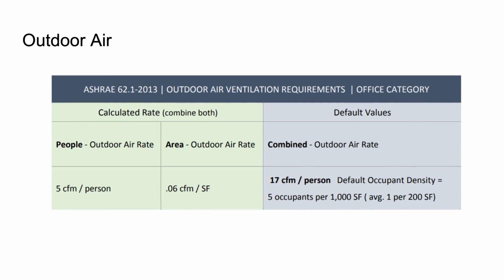Yeah, so if you have a vestibule, like an intermediary space, that's not really the term, but whatever, that space where you have an entry and then a secondary door, that area is usually going to be pressurized with the idea of preventing any mixing from outside to inside. You have it all the time in grocery stores, where you have one set of doors and then you go through a second set of doors. The whole idea is to create an area where there's heavy traffic so that you aren't having stuff go from outside to inside. Here's a little table on the outdoor air calculation.